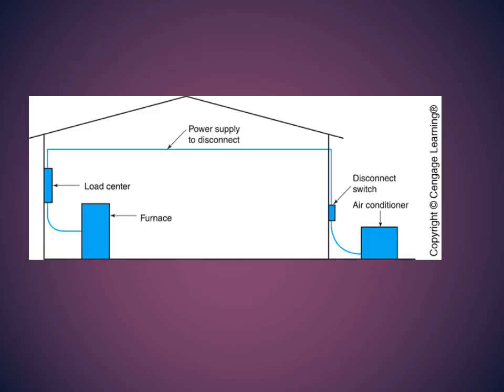So this picture will show you how we connect equipment from a load center. This is my control panel or power supply center that goes to the furnace here, and the power line goes all the way to the outside unit. And again, if you notice, the disconnect switch is within reach. So if you're outside doing some repair and something sparked or something didn't seem right, you can go and disconnect the switch right away for the entire system. Probably there is a switch in here and another switch in here, but that's local, and you want something that will cut off the power entirely from the equipment.